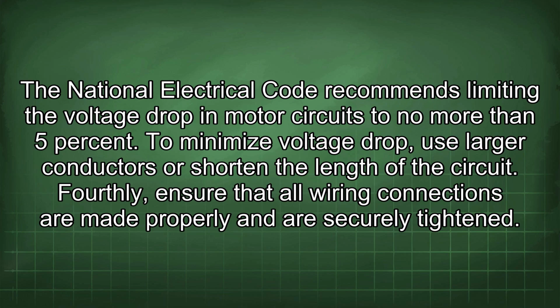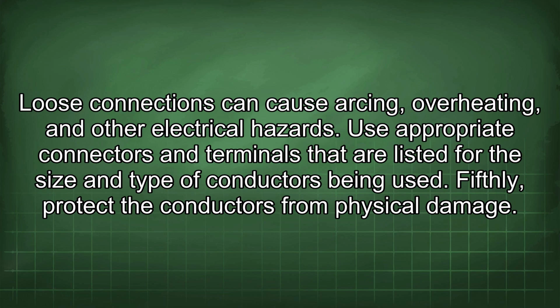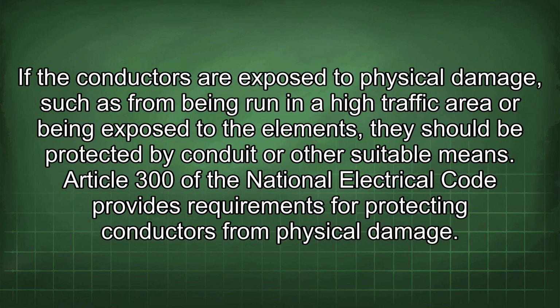Fourthly, ensure that all wiring connections are made properly and are securely tightened. Loose connections can cause arcing, overheating, and other electrical hazards. Use appropriate connectors and terminals that are listed for the size and type of conductors being used. Fifthly, protect the conductors from physical damage. If the conductors are exposed to physical damage, such as from being run in a high traffic area or being exposed to the elements, they should be protected by conduit or other suitable means. Article 300 of the National Electrical Code provides requirements for protecting conductors from physical damage.